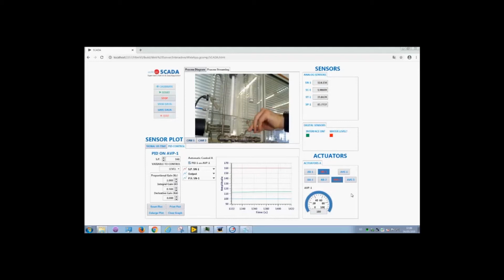Important control algorithms can be carried out, like PID. For example, the level of the tank. It is important to notice that ECL provides a bidirectional communication. Any user action on the local SCADA application is reflected on the browser too. Set points and process variables for the PID control are displayed on time charts. The actuation is increasing rapidly if we observe the proportional valve AVP1. To observe better the PID control, the valve AVS1 is open. Therefore, the tank will empty as we try to reach the established set point of the water level. In order to reach the set point faster, half of the tank will be filled, closing manually the leveling valve.